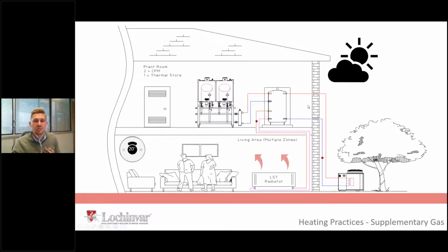And by having a hybrid system, what they managed to do was basically the air source heat pump's only actually sized to an outside air temperature of about 7 degrees. Anything beyond that, and it's not capable of the full load. So it gets colder than that outside. The heat pump kilowatt rating no longer matches the building rate. Or someone turns the thermostat up, which is also typical in care homes. You design to 20, but that could end up being any number. And the outside air temperature drops. Kilowatt requirement on the building increases.